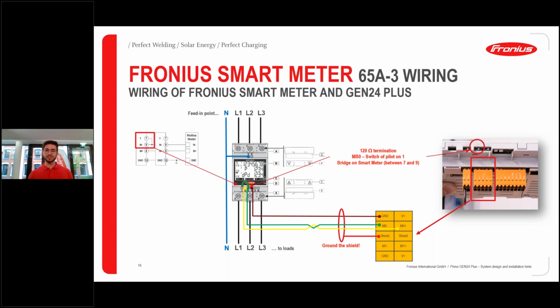Yeah, the biggest, most important thing is, of course, the data communication. Or before we come to the data communication, where do I mount this product? Of course, I have to answer this question first. The Fronius smart meter is installed at the feed-in point, so directly after the utility meter. Then we want to install the Fronius smart meter usually, because then we have a very central position where we can measure all the energy flows within our system.